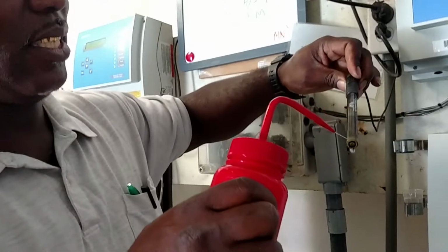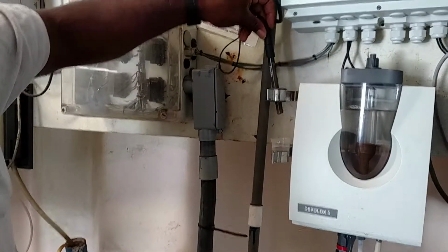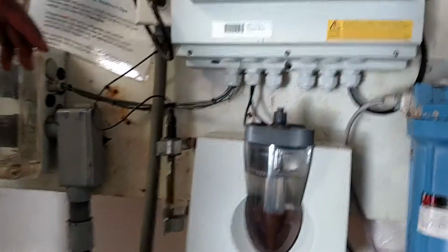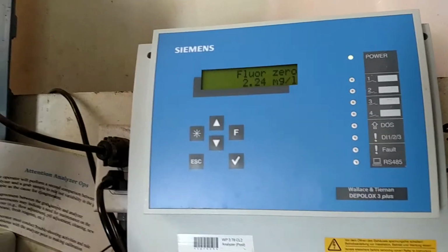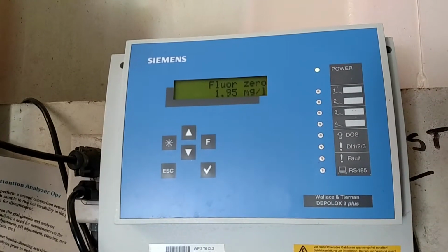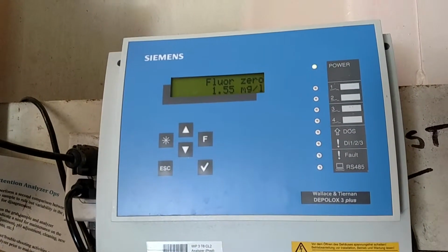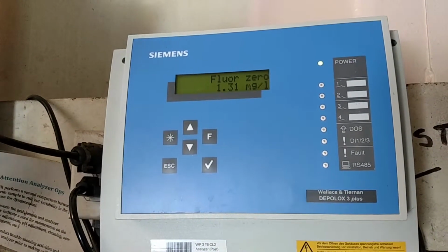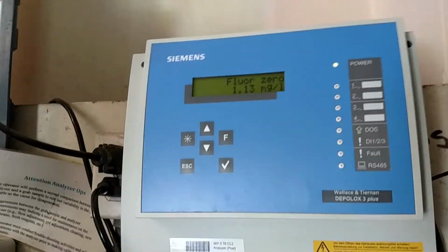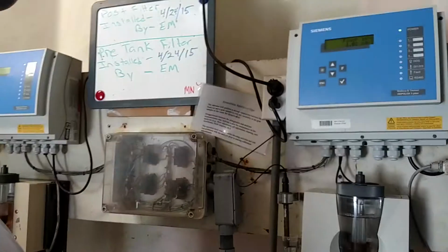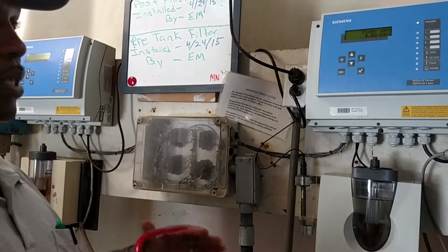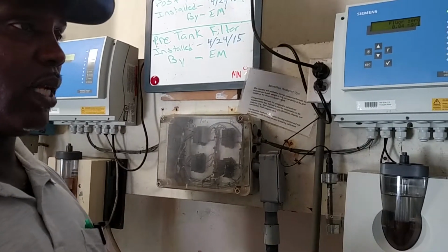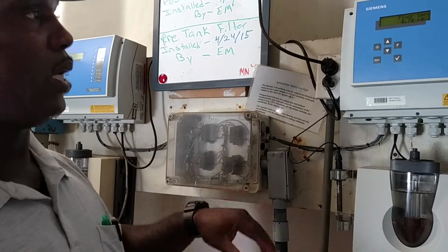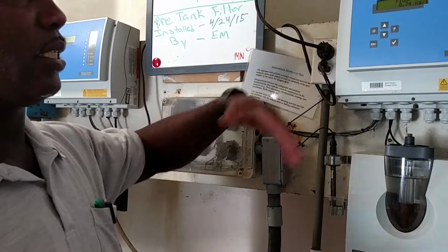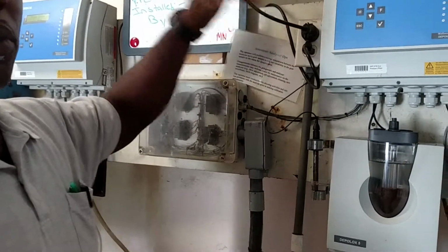So I come here and I basically just rinse it off, set it in my standard. And normally some of these, I don't know if it's an internal delay, it might take maybe 15 to 30 seconds before it actually starts reading. All you gotta do is just be patient. Then if the probe does work, you can just let it drift itself back down to the 0.2. Once it gets to 0.2, and sometimes it may get there, may not, may go below. I give it usually like a good minute, and as long as it's kind of stable, what I end up doing is hitting the check mark. That gets me into that 0 calibration, then I take it to 0.2. Once I take it to 0.2, then I end up going to the next one.